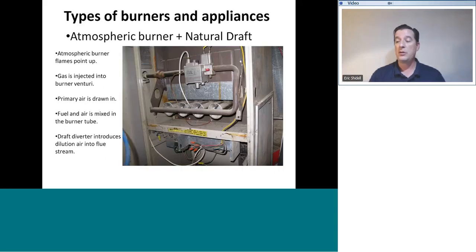Here's a good shot of an older natural draft atmospheric burner furnace. Here you see the gas control valve discharging into the gas manifold, and the orifices are in line with the burners, injecting gas down the length of the burner tube. These openings in the end are the venturi openings, and that is where the combustion air is drawn in to mix with the gas. This is where primary air is drawn in. And on a lot of these burners, you'll actually find a shutter here where you can open and close this opening to control the amount of primary air being drawn in.